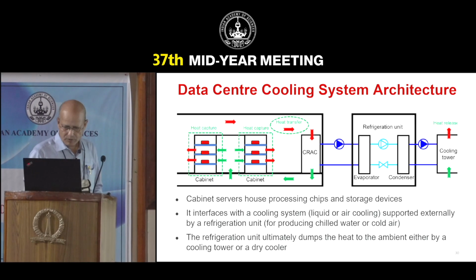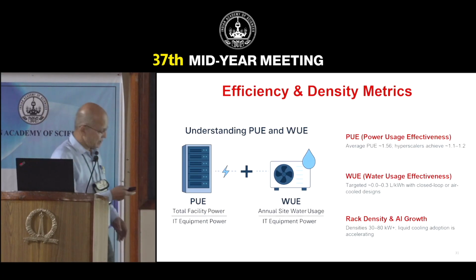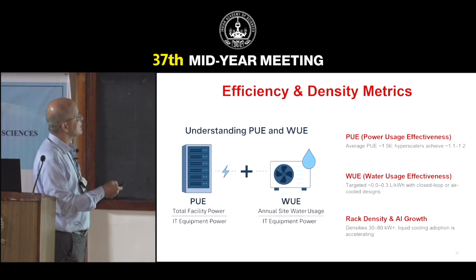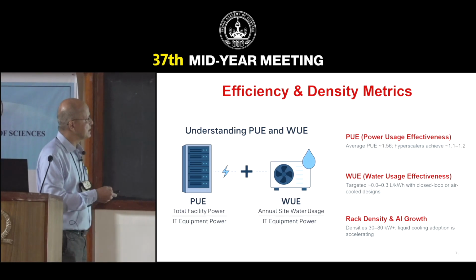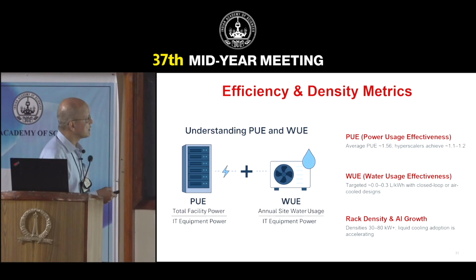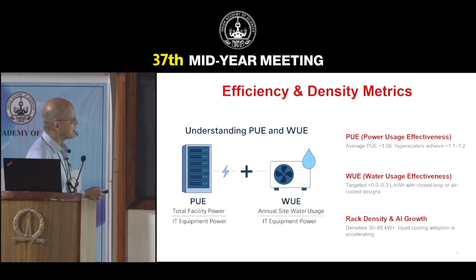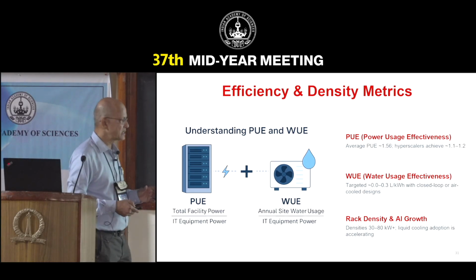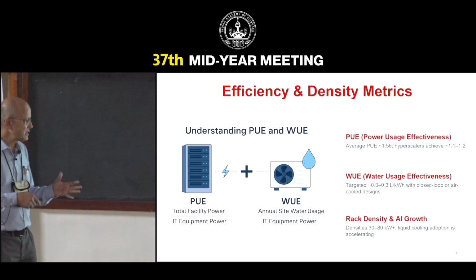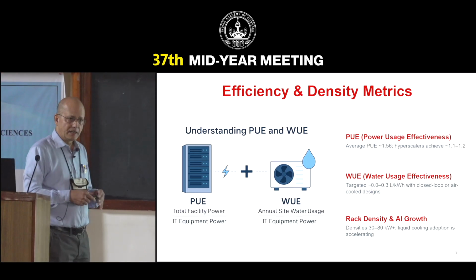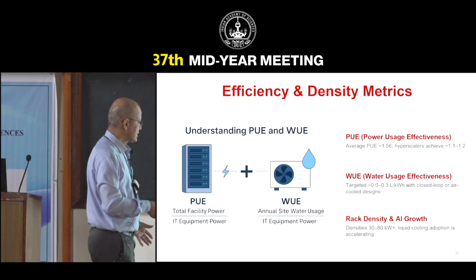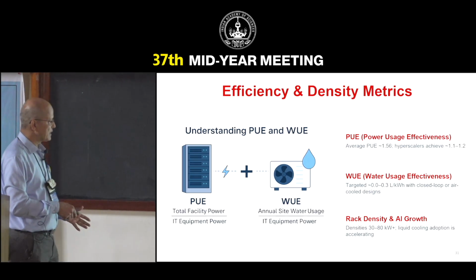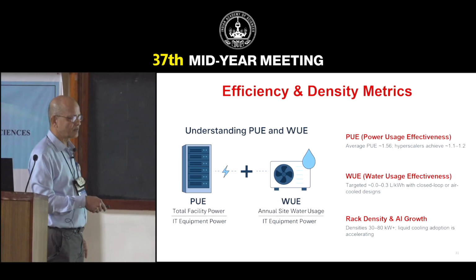So with that background, let us look at the quantification of the sustainability indices as far as data centers are concerned. One is called the power usage effectiveness, which is the total facility power required versus the IT equipment power. IT equipment power is when we say a data center is 1 gigawatt, that means it is consuming this much. But for cooling also you need additional power, so that's where the total power comes in, and this is obviously greater than 1. How much greater than 1 is what we are looking at.